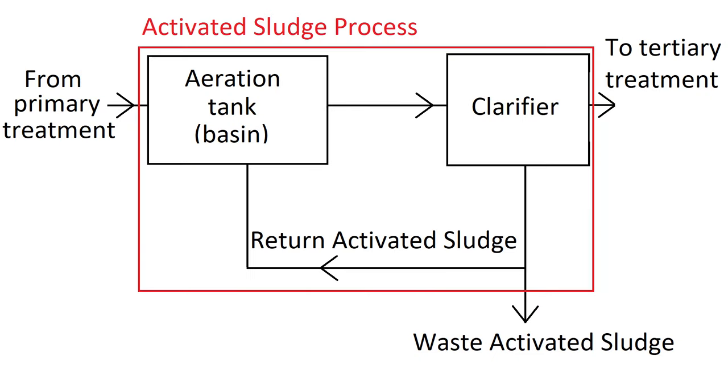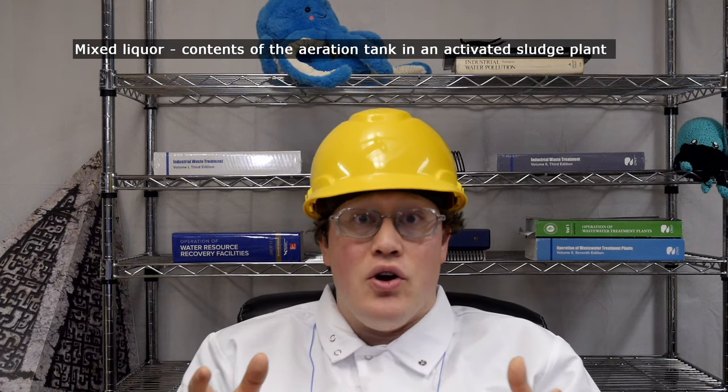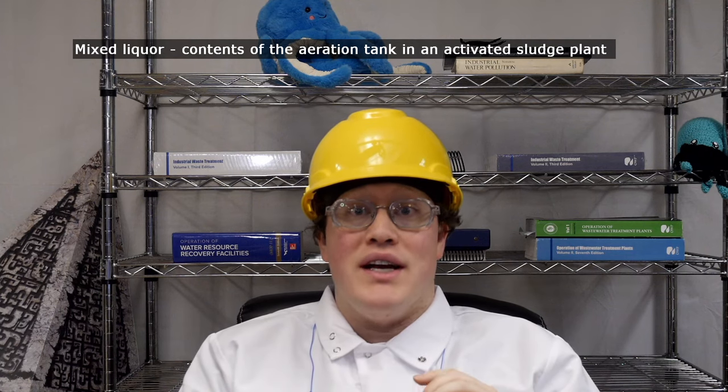This part of the diagram is where the activated sludge process is actually happening. The physical requirements are pretty simple — you need a tank to contain all the wastewater and microbes. The industry term for the contents of this tank is 'mixed liquor,' although this definitely is not the kind of liquor you would want to drink. It turns out the microbes that do the best job of breaking down pollutants are bacteria operating under aerobic conditions — in other words, using oxygen to live and grow. So this tank needs some way of adding oxygen to the mixed liquor to support these bacteria.